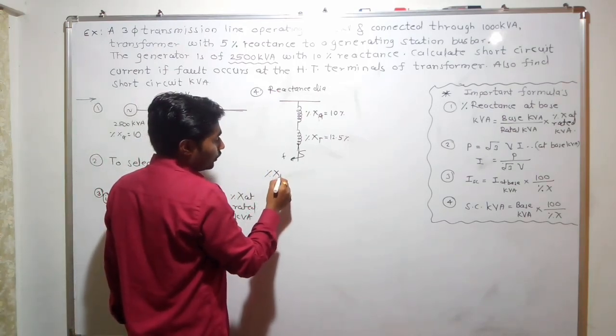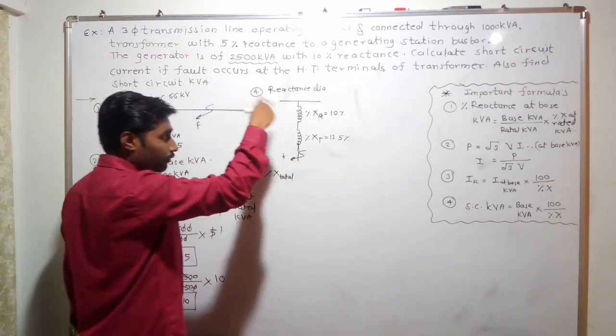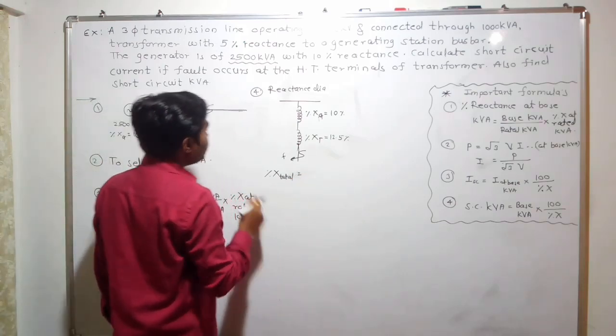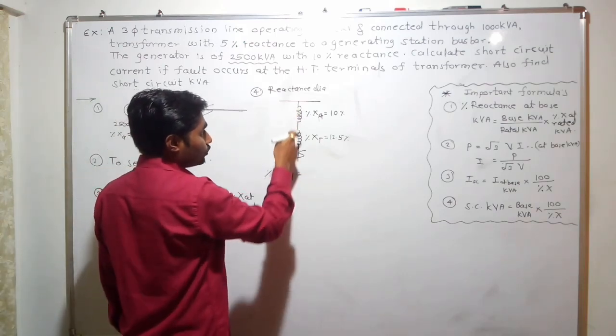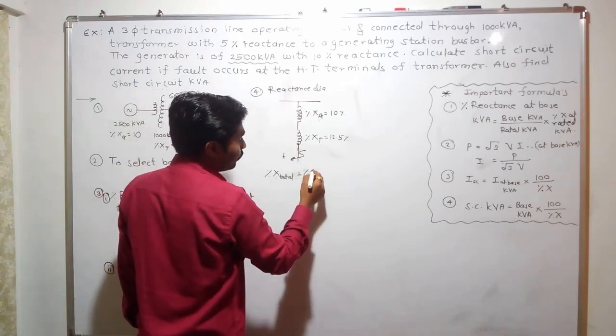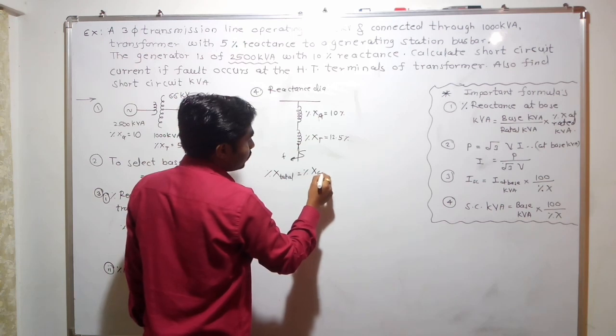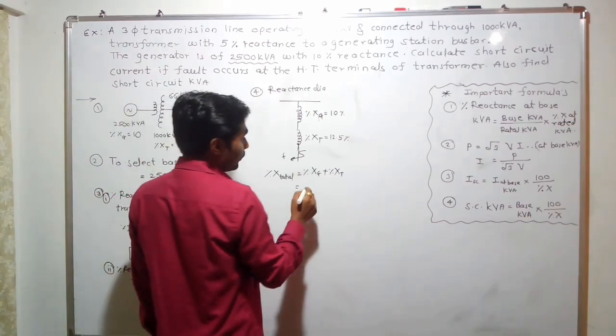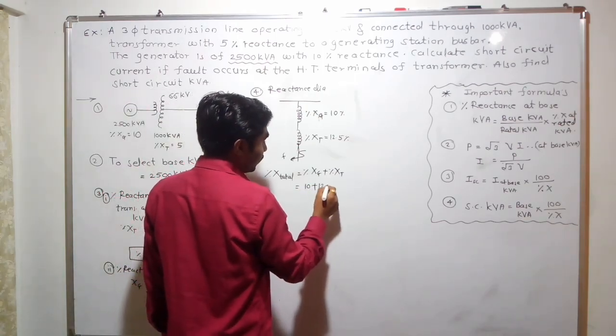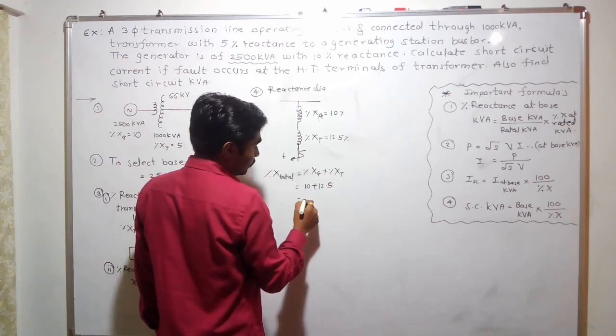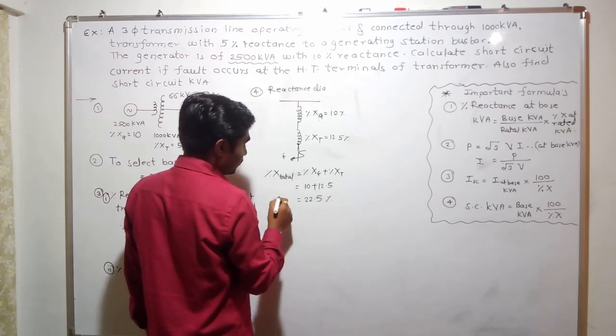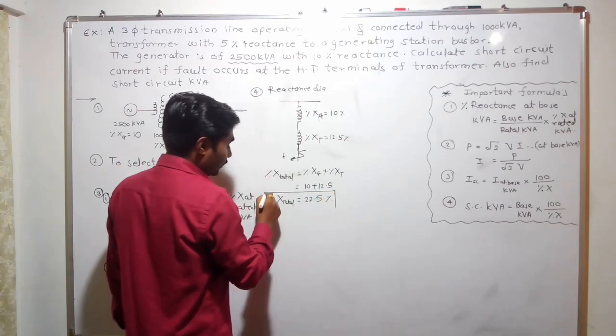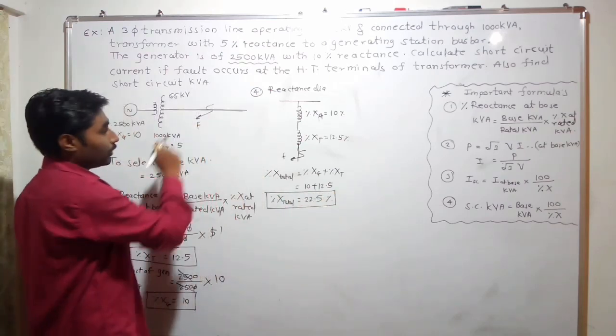Now we calculate the total reactance of the circuit till the point of fault. Since the generator reactance and transformer reactance are in series, we add them: percentage XG + percentage XT = 10 + 12.5 = 22.5%. This is the total percentage reactance of the circuit till the point of fault.